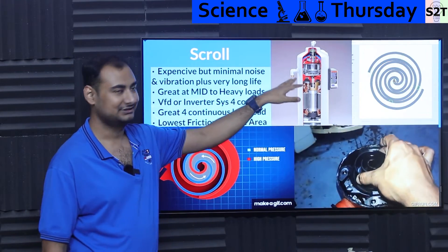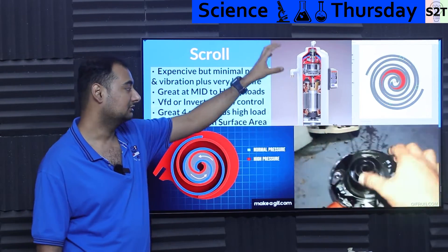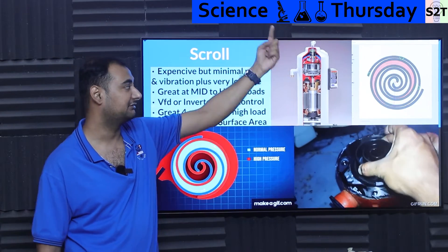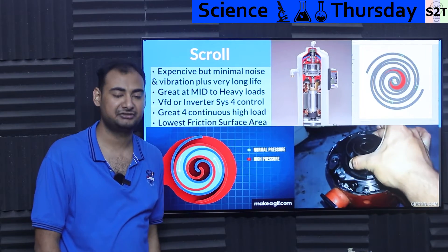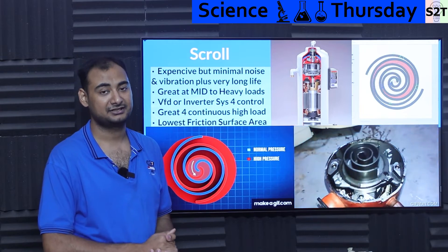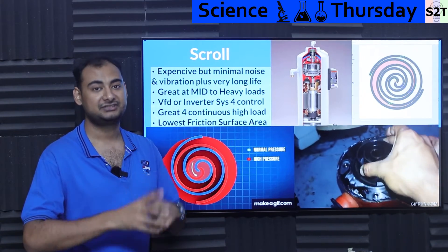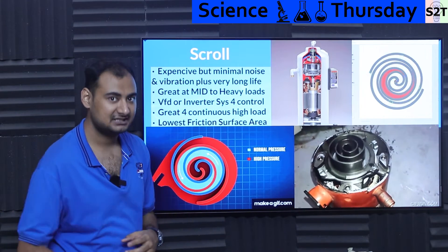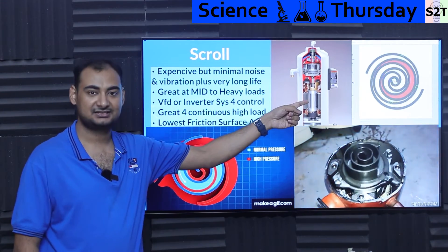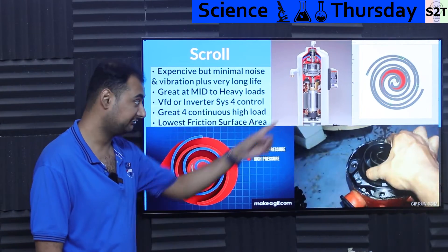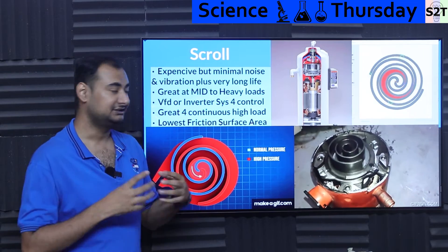How do you tell scroll from rotary? Both look like cylinders, but on a rotary the motor is on top and the compressor section on the bottom; on a scroll the motor is on the bottom and the compressor on top — so refrigerant inlet is from the top-ish section on a scroll, from the bottom on a rotary. Rotary has gone through significant R&D driven by India and China buying millions of units — now we have dual offset rotary vanes with even less vibration. But NASA uses scroll compressor technology for their mass oxygen generator — that's how robust it is.